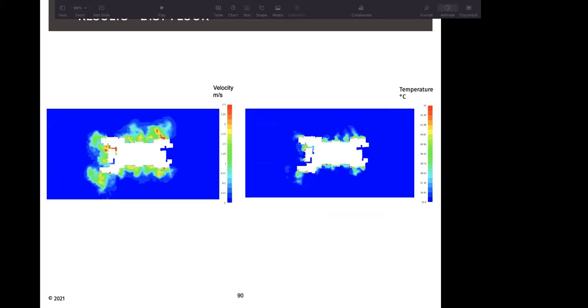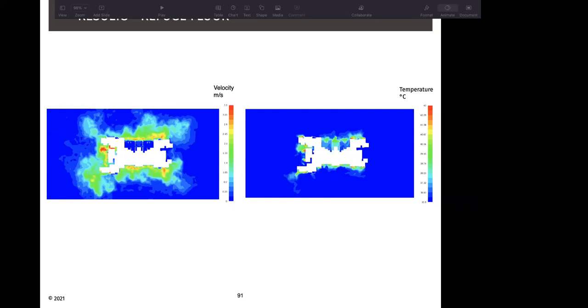But as you go to a higher level, you would see that because of thermal stacking, the velocity envelope around the building increases. There is more movement of air because the heat is rising. And we can also see that there is some heat which is moving back into the shaft, and it is affecting the inlet side of the ODU.